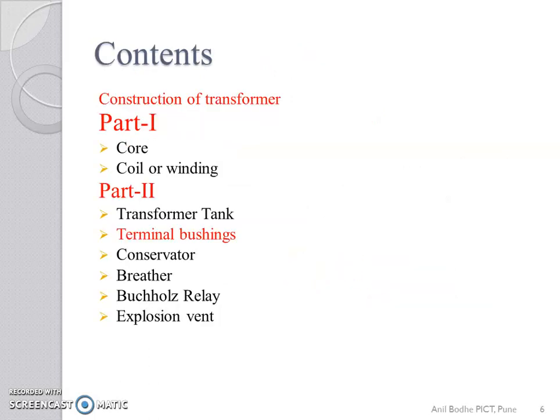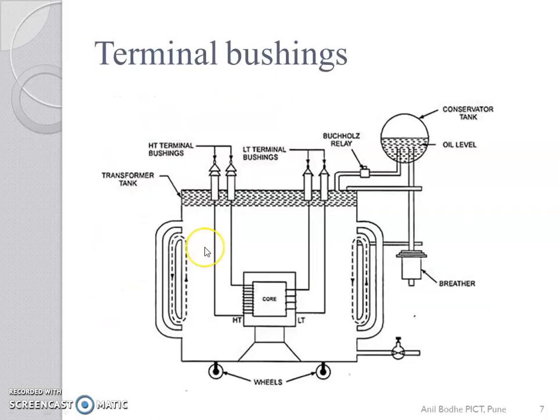Now, terminal bushing. The leads of the transformer brought out from the tank are insulated from it, meaning the tank, with the help of porcelain bushing. These bushings are fitted to the tank.